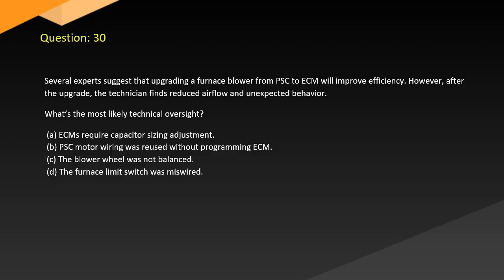Question 30. Several experts suggest that upgrading a furnace blower from PSC to ECM will improve efficiency. However, after the upgrade, the technician finds reduced airflow and unexpected behavior. What's the most likely technical oversight? A. ECMs require capacitor sizing adjustment. B. PSC motor wiring was reused without programming the ECM. C. The blower wheel was not balanced. D. The furnace limit switch was miswired.